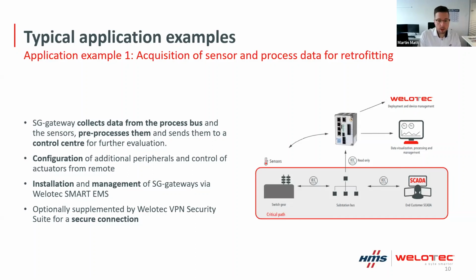We even have one customer that uses our onboard PLC, our onboard programming capabilities, to automatically hook up the sensors. So a technician just goes there, connects the SG gateway with power and network, and then installs one sensor after the other. These are Modbus RTU sensors, and they are automatically set up in alternating order, managed by the SG gateway. So the technician basically doesn't need access to any of the devices - he or she just does the wiring, and that's it.